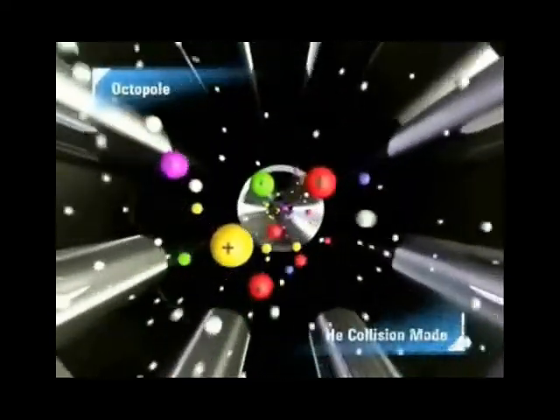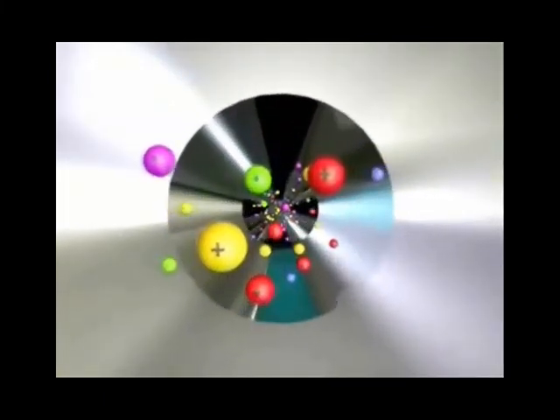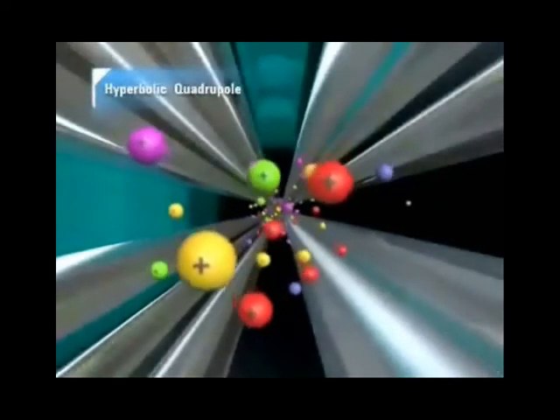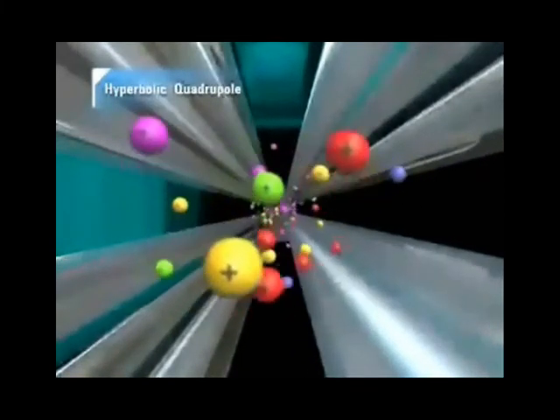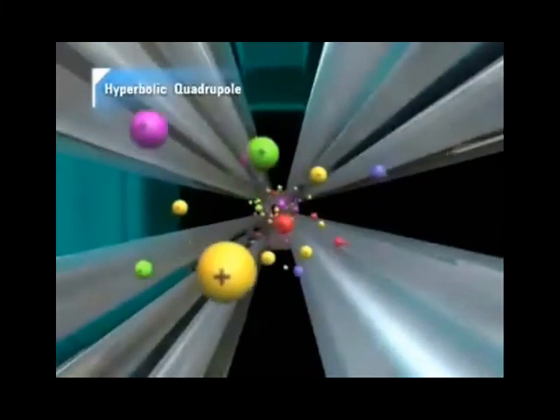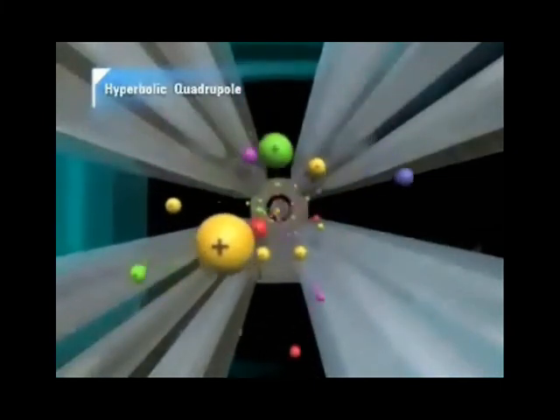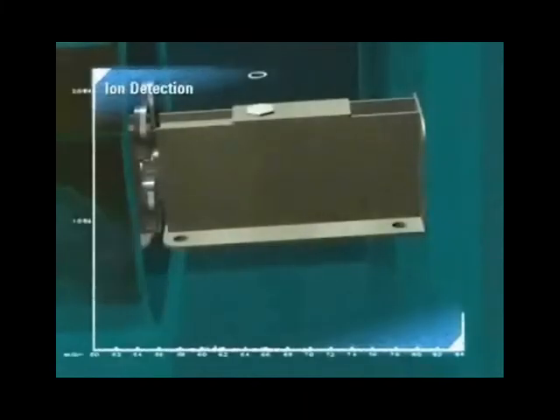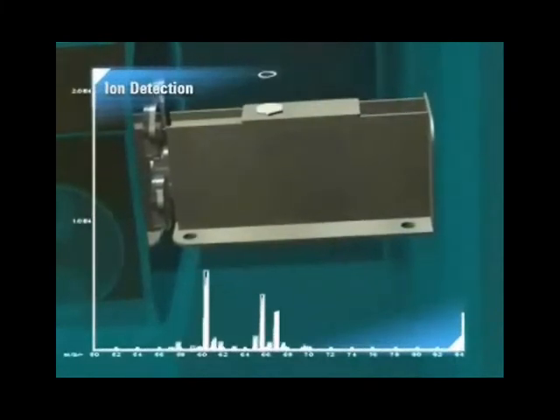The analyte ions leaving the ORS cell enter the quadrupole mass filter and are separated based upon mass-to-charge ratio. Only the target ion is stable and moves along the axis of the quadrupole. The quadrupole can rapidly scan across the mass range, passing each mass sequentially to the electron multiplier detector. The ions reaching the detector result in electronic signals that are passed by digital electronics to a multichannel scaler creating a mass spectrum in which the intensity at a given mass is proportional to the concentration of the isotope at that mass.